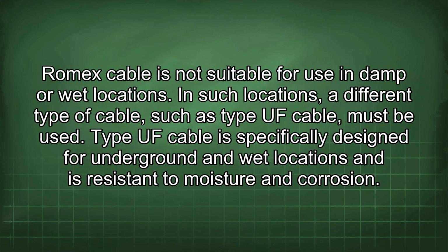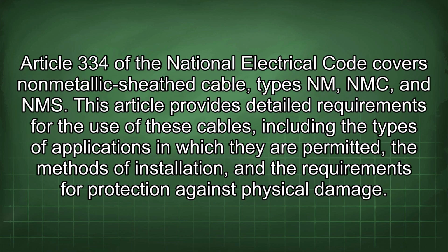Romex cable is not suitable for use in damp or wet locations. In such locations, a different type of cable, such as Type UF cable, must be used. Type UF cable is specifically designed for underground and wet locations and is resistant to moisture and corrosion. Article 334 of the National Electrical Code covers non-metallic sheathed cable, types NM, NMC, and NMS. This article provides detailed requirements for the use of these cables, including the types of applications in which they are permitted, the methods of installation, and the requirements for protection against physical damage.